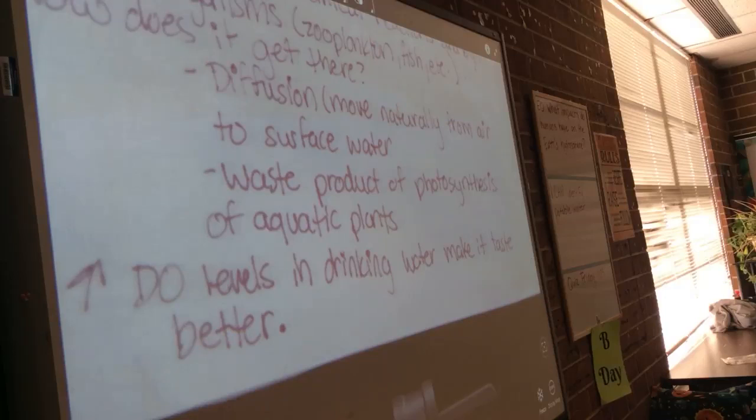Turbidity we can also use. We have a turbidity sensor, and it works a little differently than the other sensors. With the turbidity sensor, you have to follow directions carefully because it's a unit that you take the glass vial out of, and you put your test water in the glass vial and then close it up, and it reads the turbidity that way. You don't stick anything in the water. You put the water inside of the sensor.